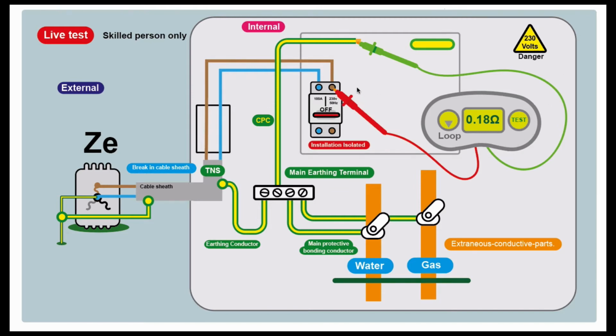When you're doing your ZE test, it's important that you don't have any parallel paths. Normally you do your ZE test at the consumer unit between the line, the main switch, and the earthing conductor, the disconnected earthing conductor. You disconnect the earthing conductor from the earthing terminal in the fuse board. But is this earthing conductor being disconnected? If we follow down, it hasn't, because there's an external earthing terminal with the main protective bonding conductors on. So if we test from here, we're getting the parallel paths of the gas and water pipes as well, and we're not getting the ZE reading of the earthing conductor and the line conductor. We've got additional connections, so we need to be careful there that we don't do that.